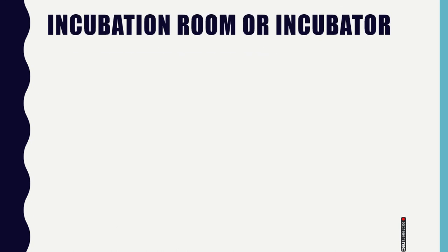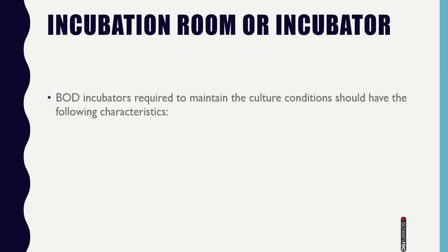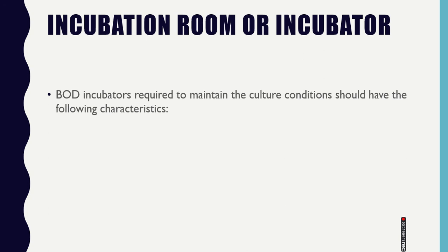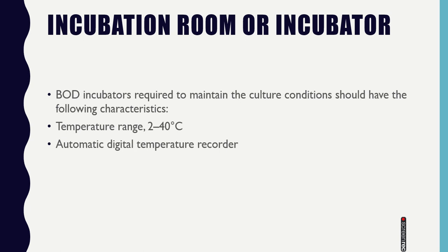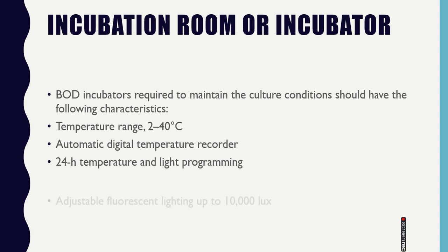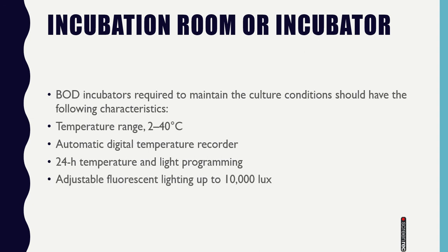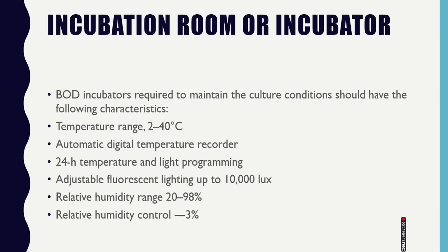Now about the incubation room or the incubator. BOD incubators required to maintain the culture conditions should have the following characteristics: temperature range from 2 to 40 degrees Celsius, automatic digital temperature recorder, 24-hour temperature and light programming, adjustable fluorescent lighting up to 10,000 lux, relative humidity range from 20 to 98%, and relative humidity control of 3%.